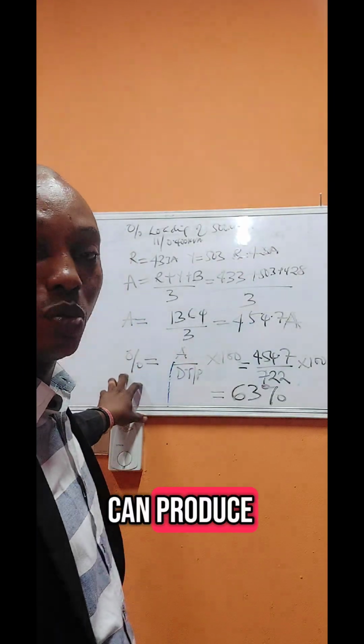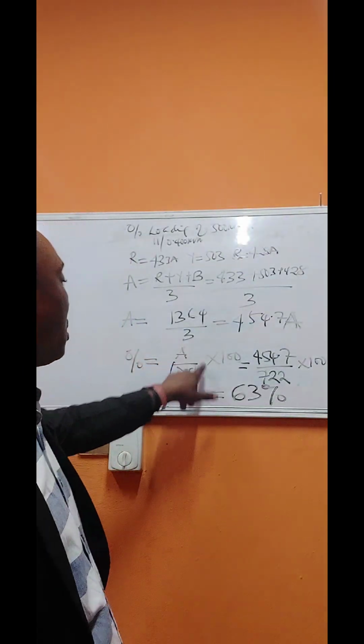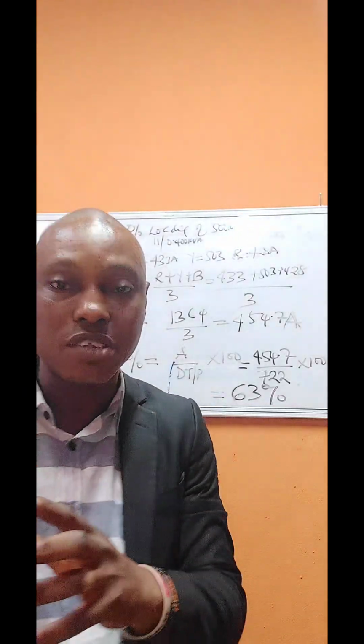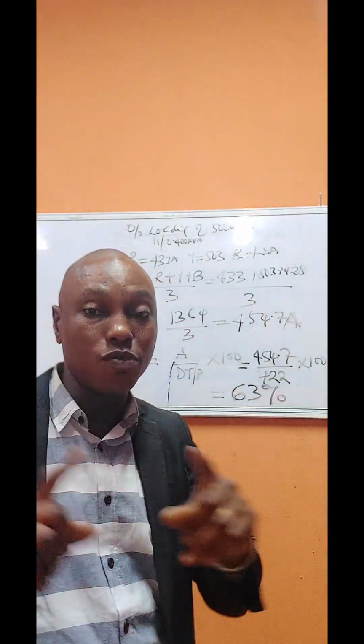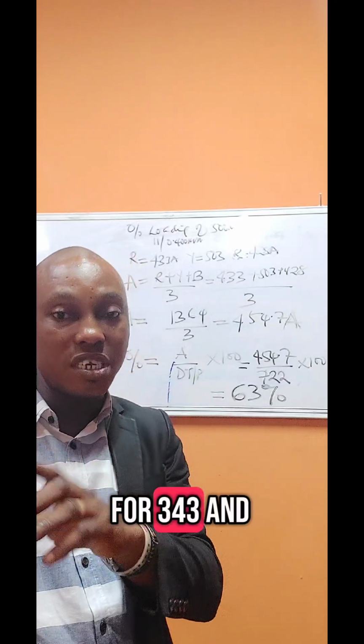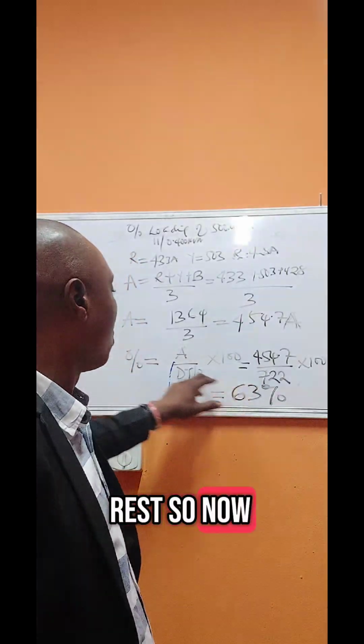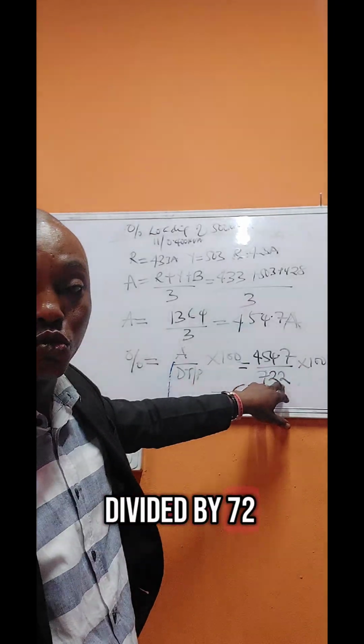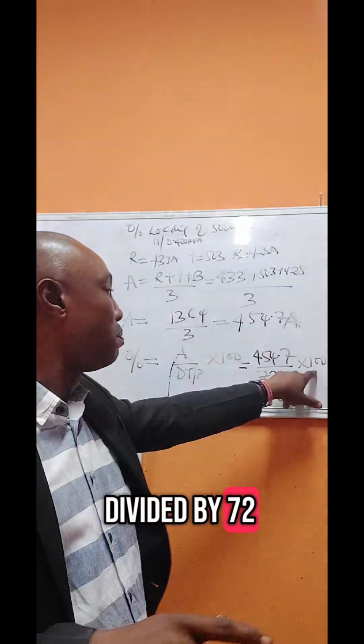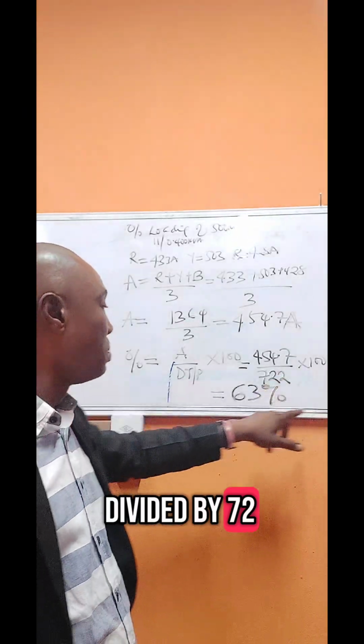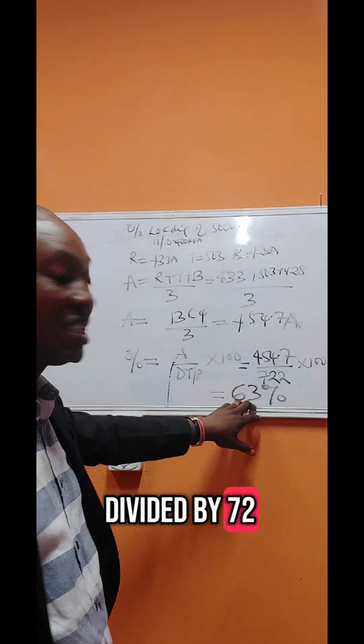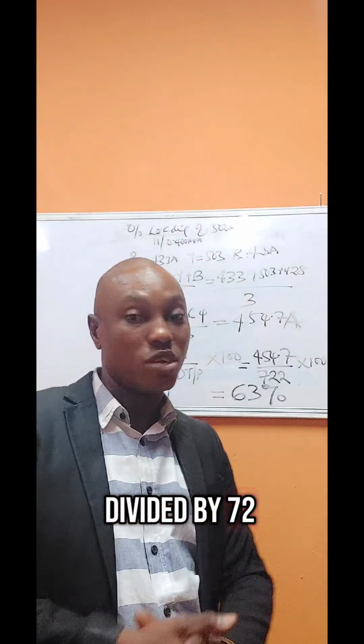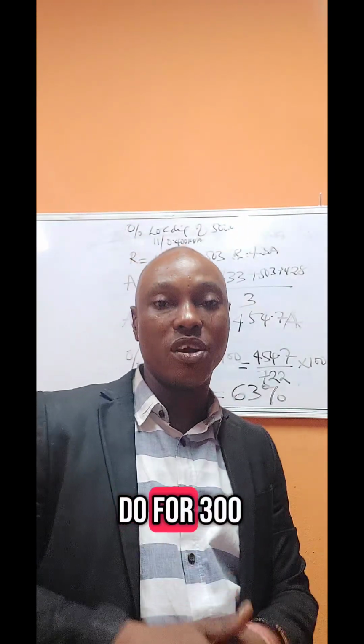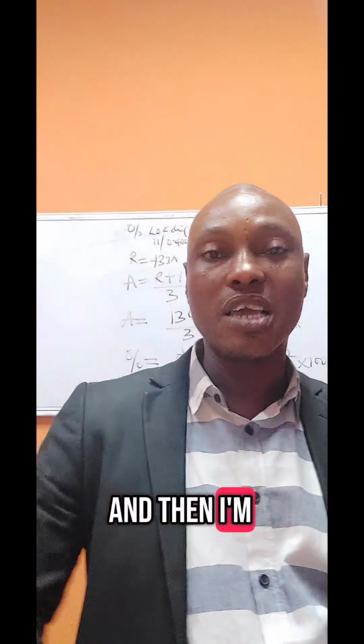Then now with the percentage load, it is the average load over the load per phase of the transformer. I told you 500 kVA can give us 722. For 300 kVA, 433, and you calculate for the rest. So now divide by 722, which is per phase of the 500 kVA transformer, and multiply by 100. So this transformer you are seeing here is going to be 63% loading. So it's not overloaded. Let me do 300 kVA as well, and then I will give us the classwork.